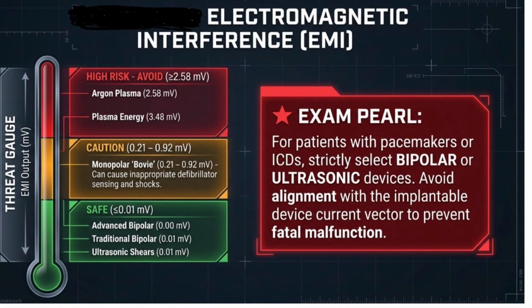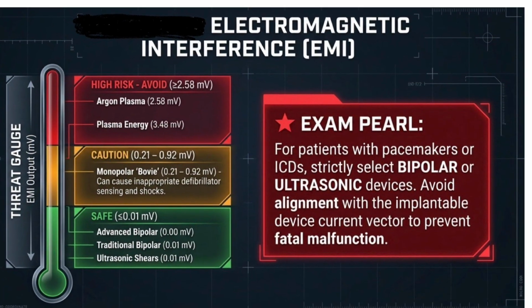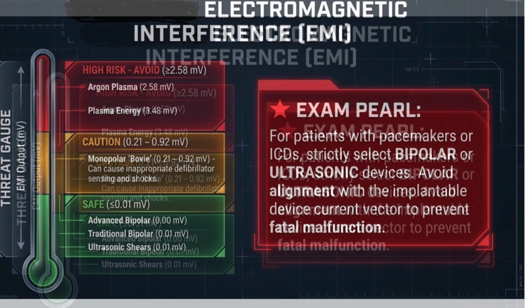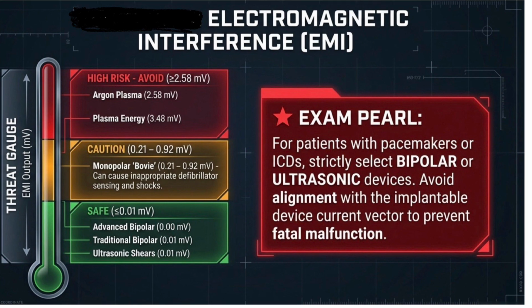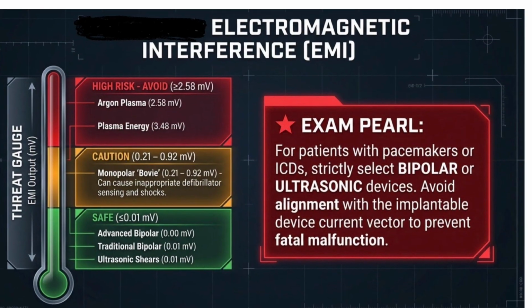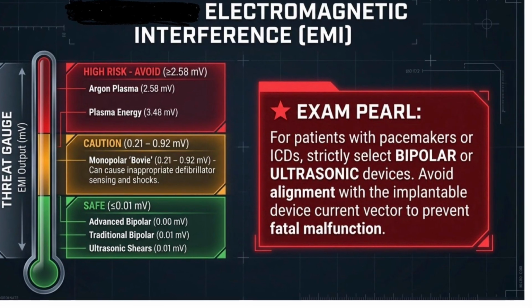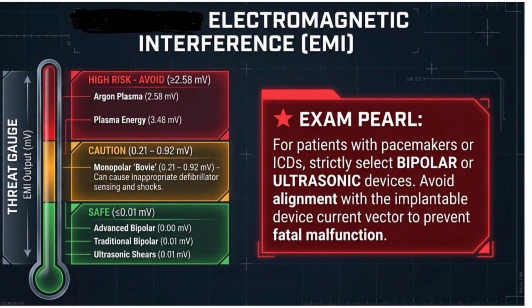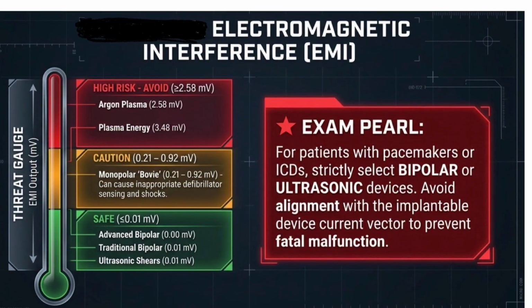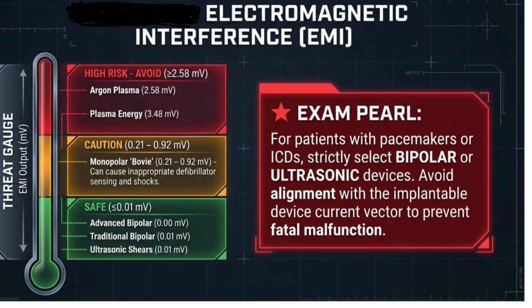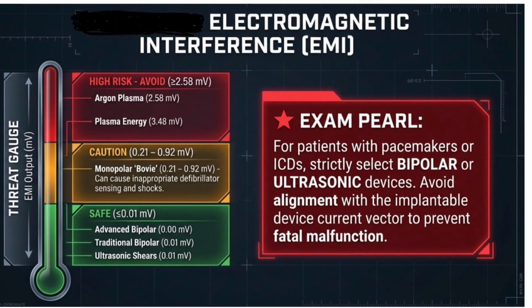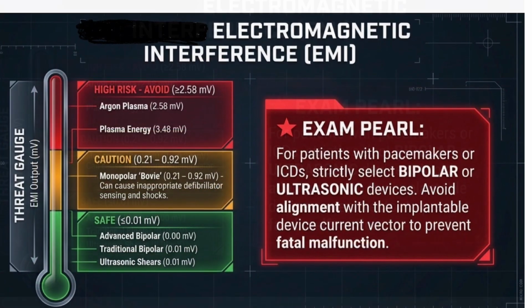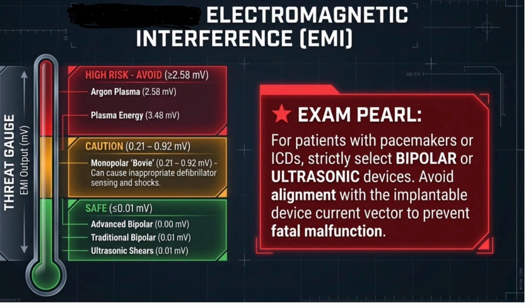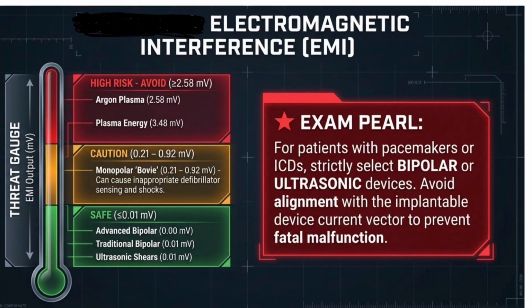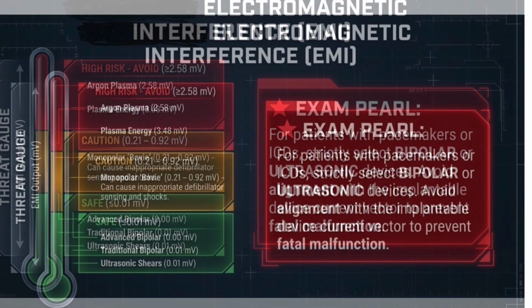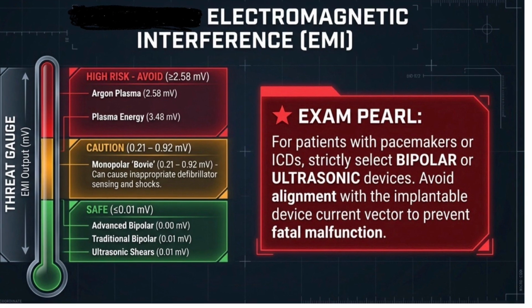Electromagnetic interference. The safe ones are the advanced bipolar, traditional bipolar, and the ultrasonic shears. Caution needs to be exercised while using monopolars, with a strength of 0.21 to 0.92 millivolts, as they can cause inappropriate defibrillator sensing and shocks. At high risk are the argon plasma and the plasma energies, which have more than 2.58 millivolts of energy and can cause damage. For patients with pacemakers and intracardiac defibrillators, strictly bipolar or ultrasonic devices should be used, and alignment with the implantable device current vector should be avoided to prevent fatal malfunction.